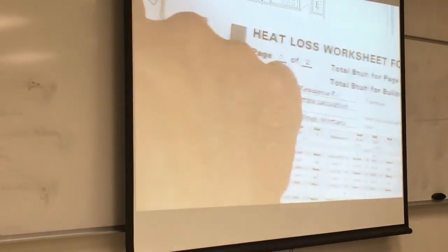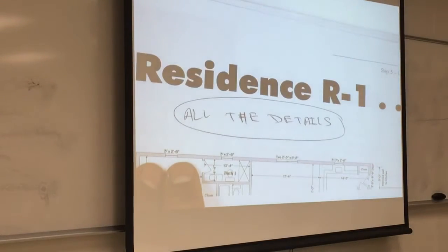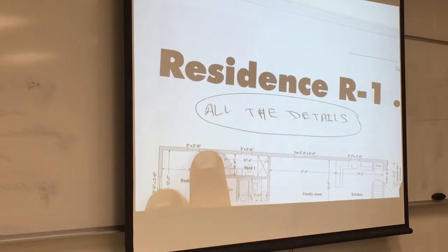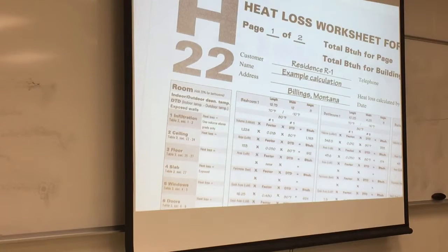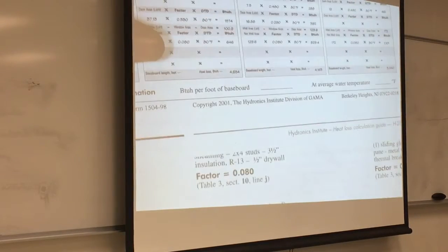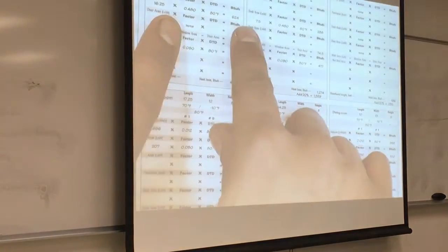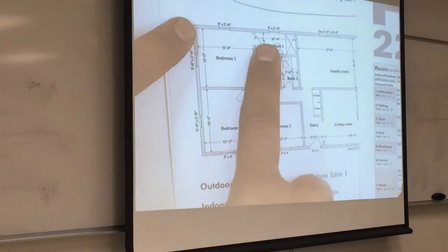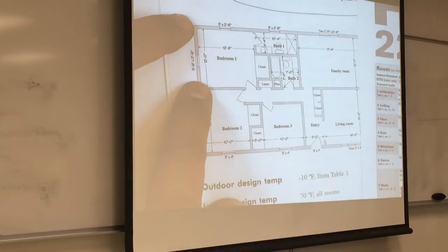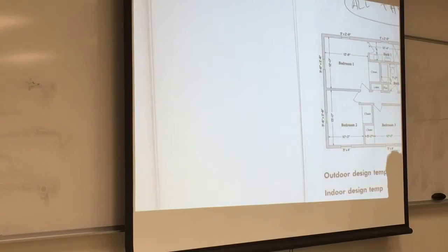Windows, here are the windows. We calculate the area of the windows, which is this number. These numbers multiplied together, plus this number. 2 windows. Total area is 16.25. Factor, you get the factor from here. Walls, 182, which is this wall, plus this wall, minus the windows.